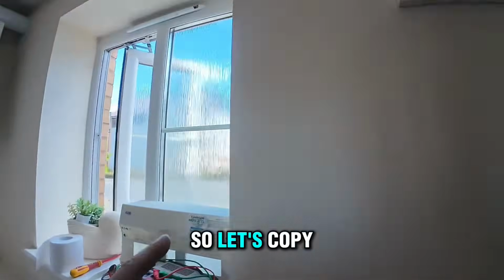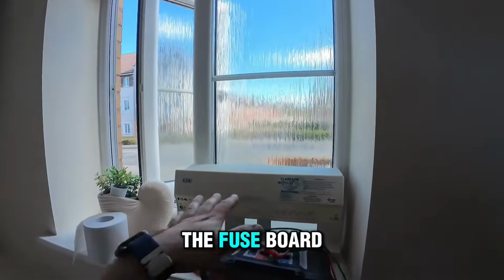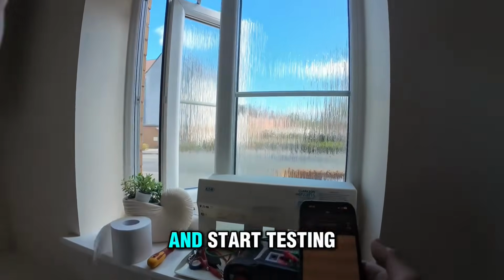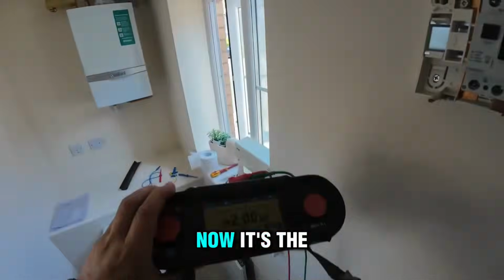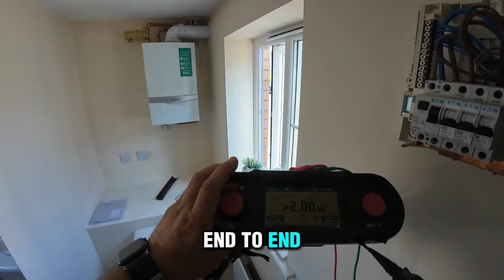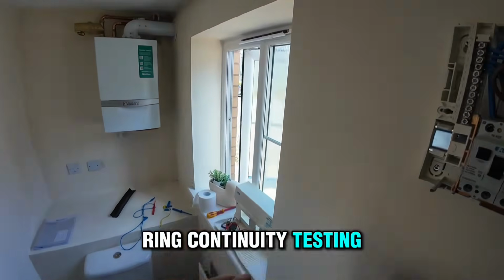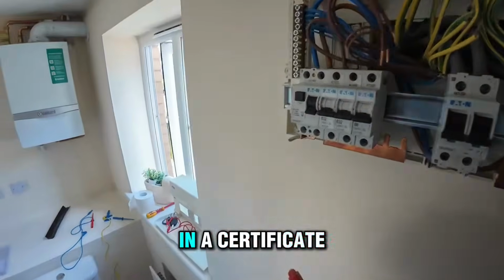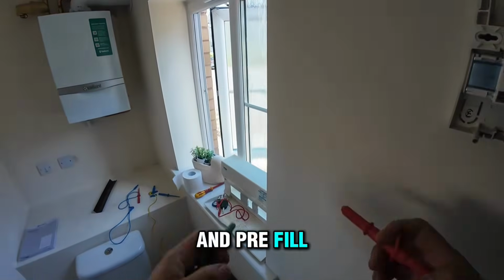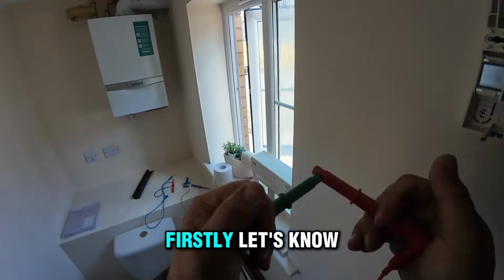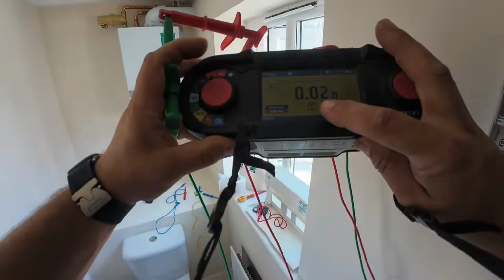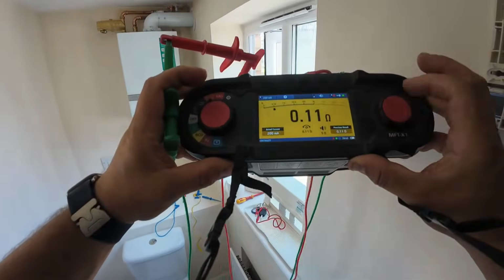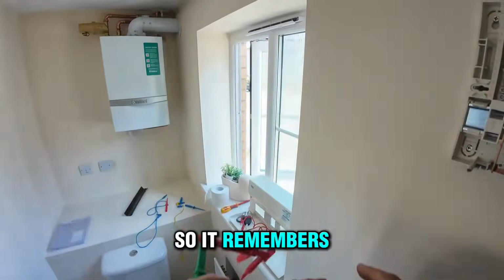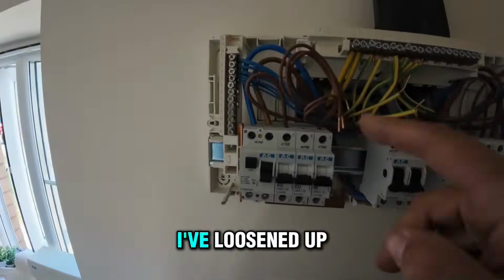So let's copy the details from the fuse board onto this and start testing. So now it's the time that we need to do end-to-end ring continuity testing. It took me 15 minutes to put the information in a certificate and pre-fill the table. So firstly, let's null the leads. It's 0.09. Here we go. So it remembers the resistance of the cables. I've loosened up the screws.